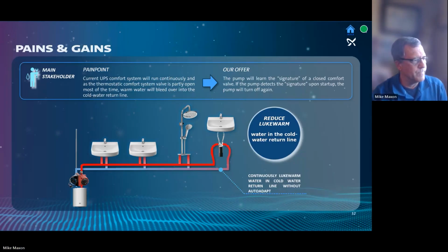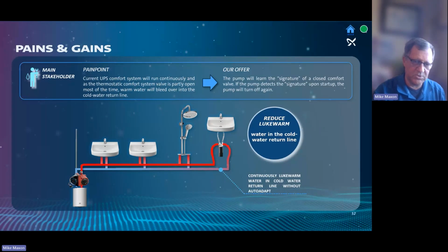For the comfort system, this image here is the old comfort system. This would be the new one. But now it's going to shut off. The first time it runs, it's going to run for about 2 hours looking for what the wattage is of a closed valve. It's going to learn what a closed valve is by wattage. And then from that, it'll always shut off at that wattage. And so when it knows the valve is closed, it shuts off, prevents that bleed over. And then I think it's off for about 15 minutes, it'll run again. I have a few test sites out right now, and the people I'm hearing from say that does work. They're not getting the warm water on the cold side.